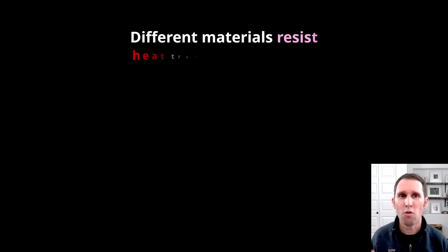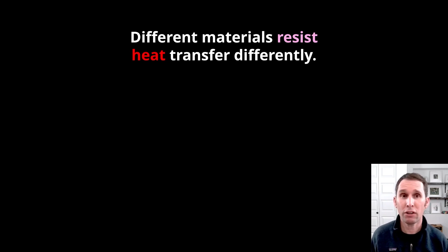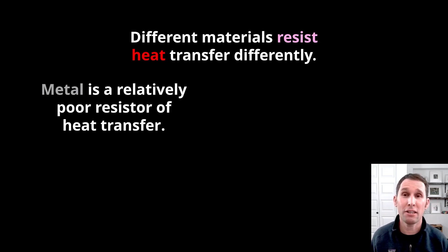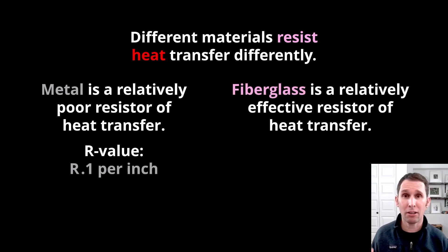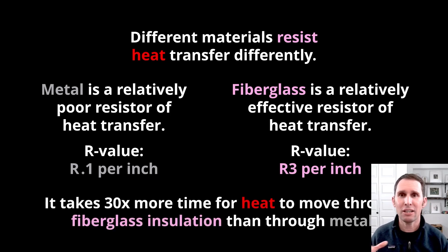So, different materials resist heat transfer differently. Metal, for example, is a very poor resistor of heat transfer. It's very good at conducting heat transfer or moving heat. It's got a very low R-value of about 0.1 or one-tenth. Fiberglass, on the other hand, is a relatively effective resistor of heat transfer. It's got a higher R-value of R3 per inch. So, it takes actually 30 times more time for heat to move through fiberglass insulation than it does through metal.